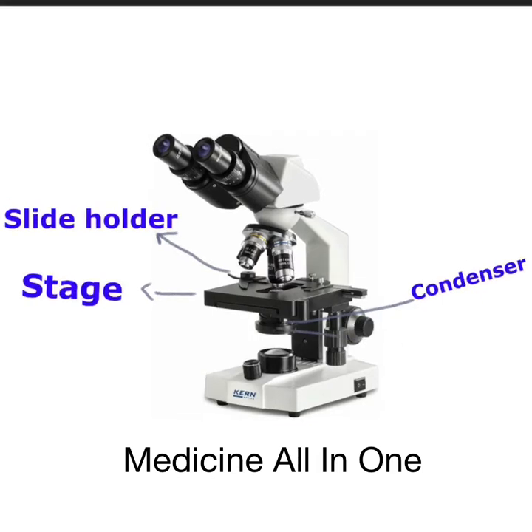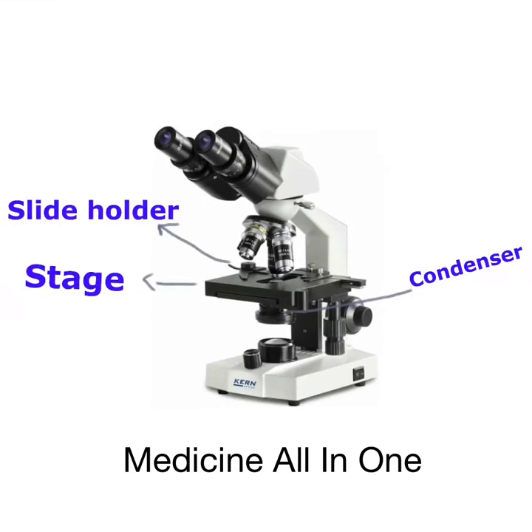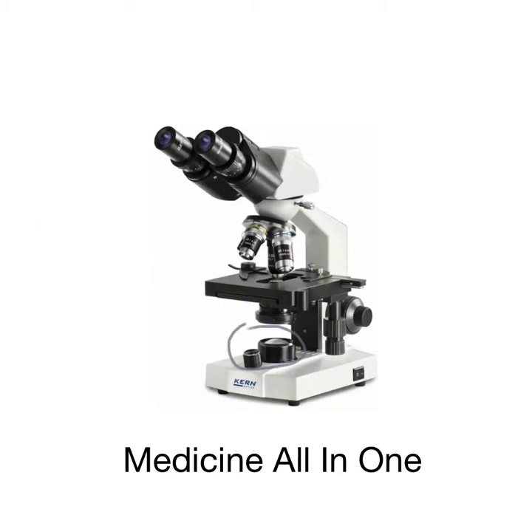Below the stage there is a condenser. The condenser basically focuses the light from the light source onto the slide. In an unstained slide it is adjusted at the lower position, whereas in a stained slide it is adjusted at the higher position, that is one to two millimeters below the slide. On the condenser there is a small lever known as the iris diaphragm lever, which controls the amount of light that passes through the condenser. Directly below the condenser there is the light source.